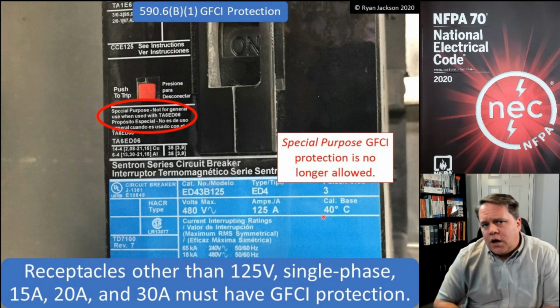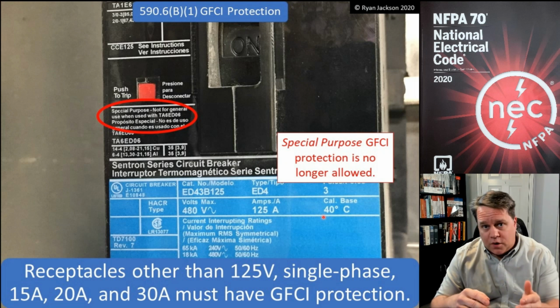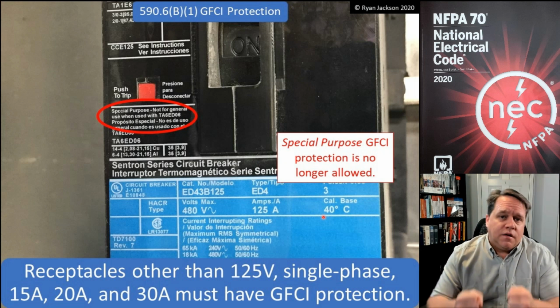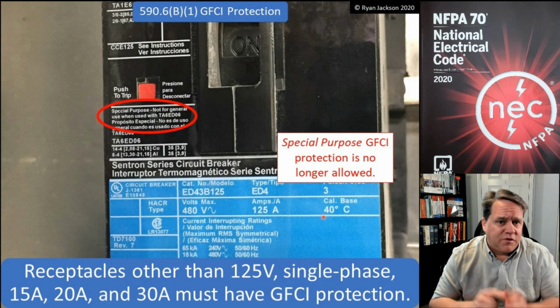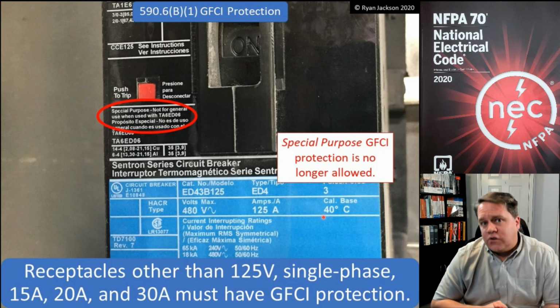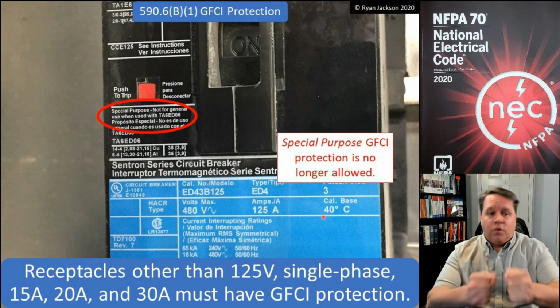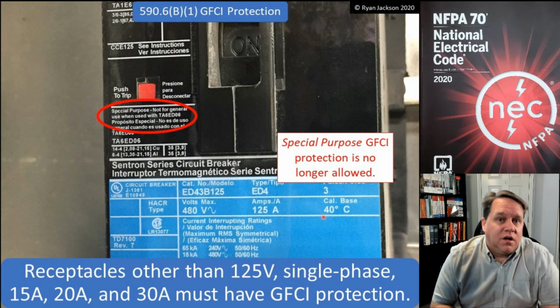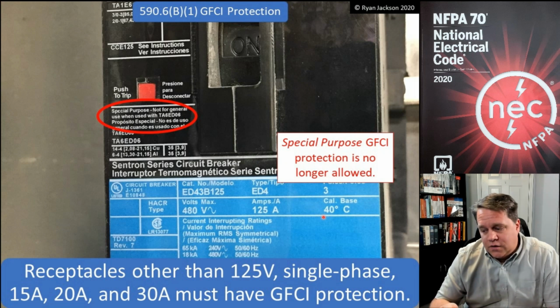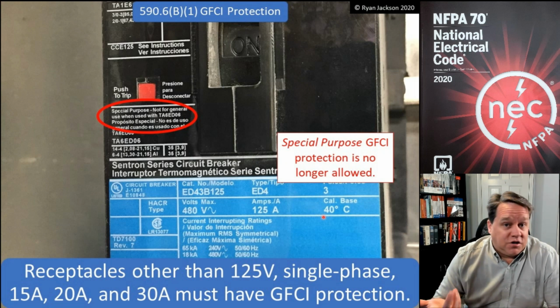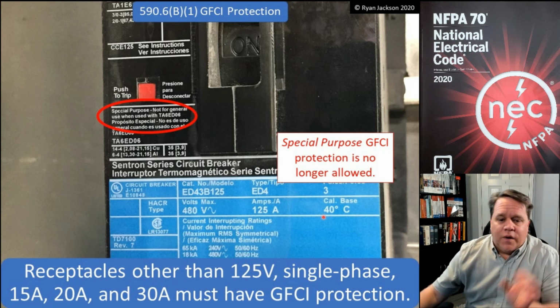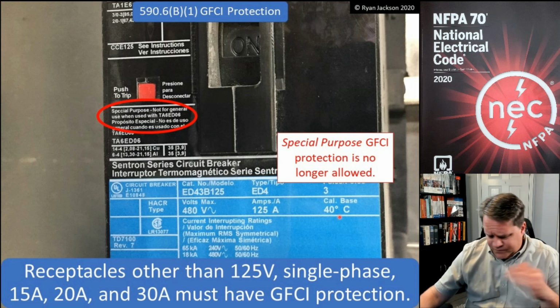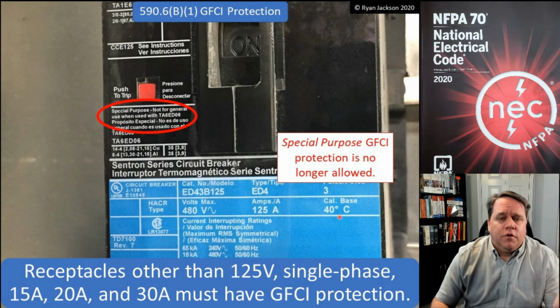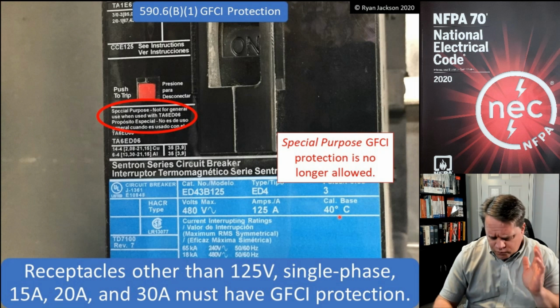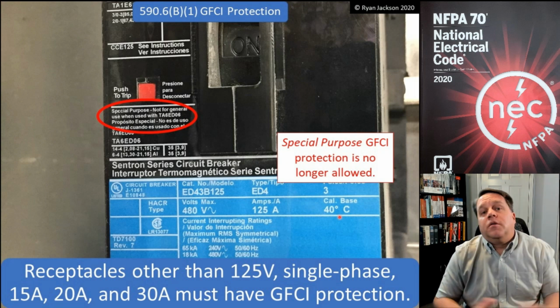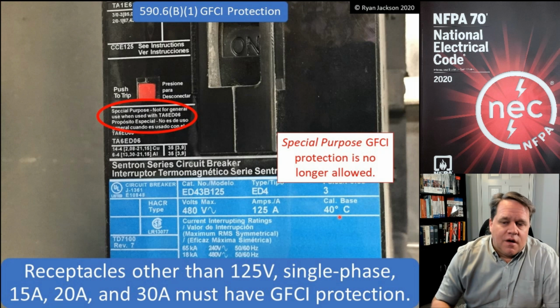But sometimes we're talking about trip points that are greater than the maximum let-go threshold. So a special purpose GFCI would stop you from dying, but it would still allow you to get hung up on the circuit and receive a very painful shock, and it wouldn't necessarily protect children from dying. So we had language about special purpose GFCIs. It survived three years and then was removed immediately in the 2020. So we have to have GFCI protection pretty much for all receptacle outlets.